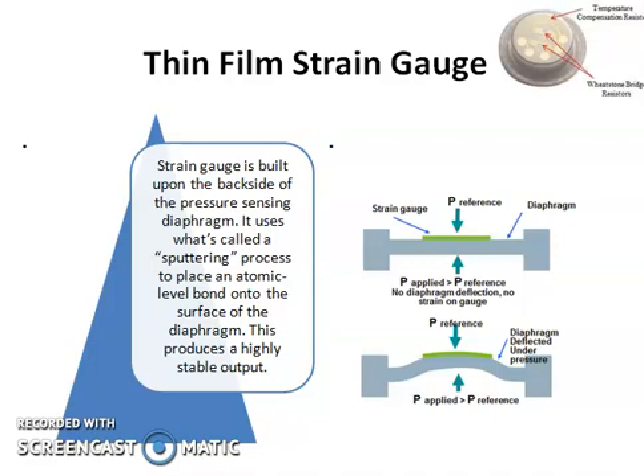Hello, in this video we are going to study the thin film strain gauge pressure transducer. It is a type of resistive pressure transducer. That is, in the case of a resistive pressure transducer, the strain gauge is mounted on the diaphragm. Whenever a pressure is applied, there will be a compression or strain in the strain gauge which is mounted on the elastic diaphragm, and the strain occurring in the strain gauge is directly proportional to the pressure applied to the diaphragm.